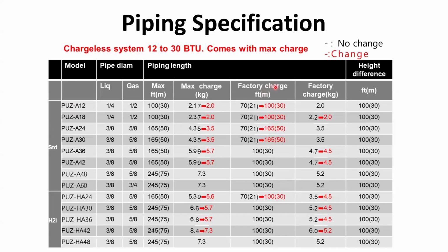And what it has done is, so the factory charge, so the footage before was 70 feet of piping. Anything above that, you have to add additional charge. Well, now we're good for 100. That's the changes they made here. 100 feet, 100 feet, 165. That's what they're showing here on these units. So again, you notice it's not all models. You have to know your model.